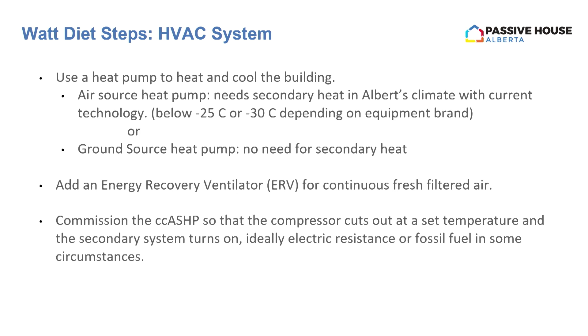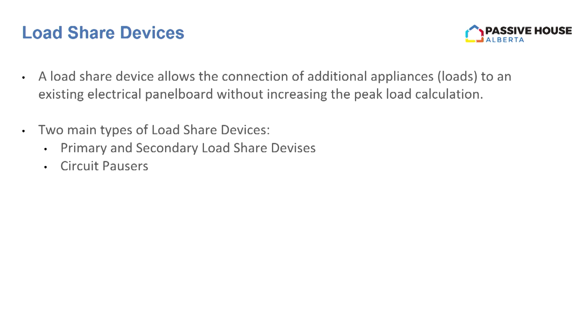And then if we've done all of that and we do the electrical code calculation and we're still over that 100 amps, this is when we start to bring in what are called load share devices. Load share devices are any device that allows you to add an additional appliance to your electrical panel without impacting that code calculation. And it does that by controlling when that connected appliance turns on and off. And there are 2 basic types of them. This is another place where nomenclature will vary. The most common words I've used are a primary and secondary load share device. This just has 2 ones and one or the other works. Or a circuit pauser. This is where it just monitors the main and either turns that connected circuit on or off. But basically, it's the 2 ways to control when this additional appliance can turn on.